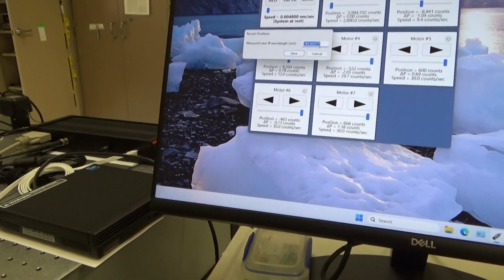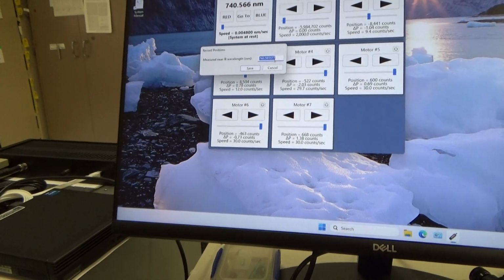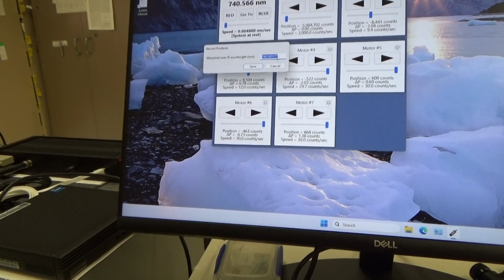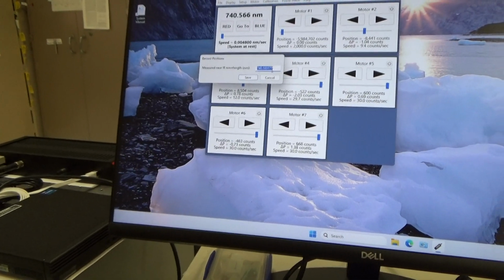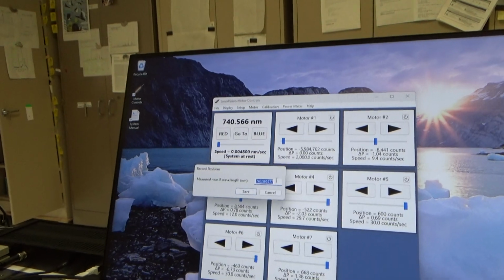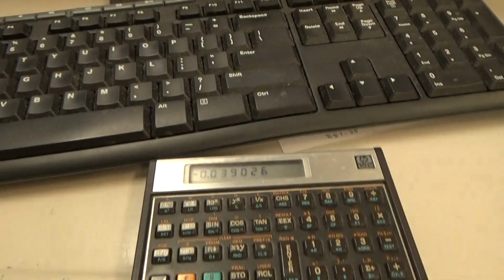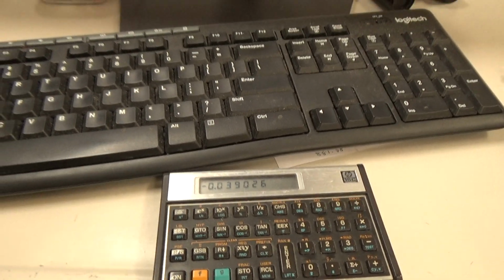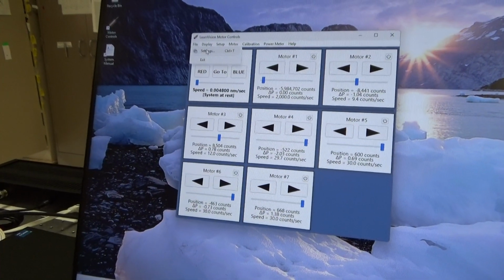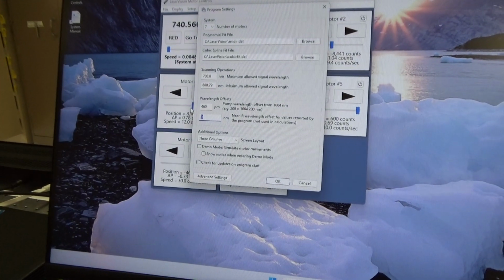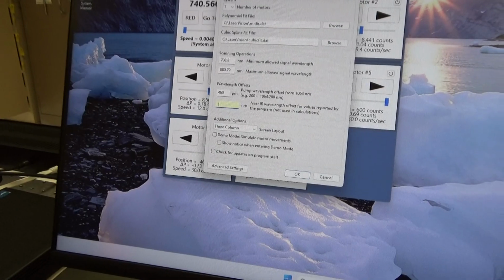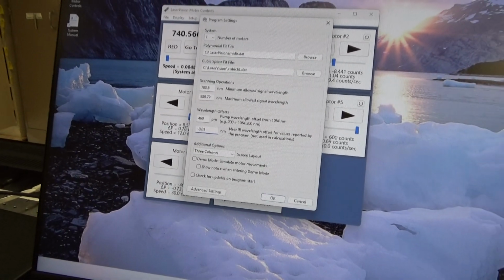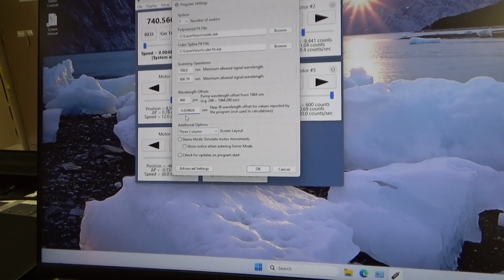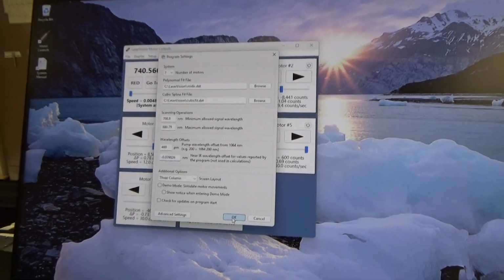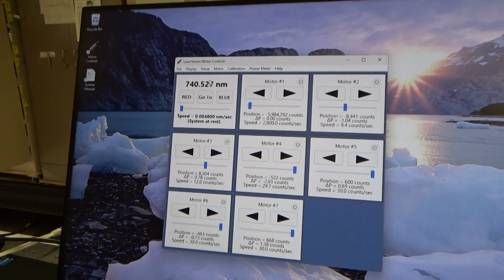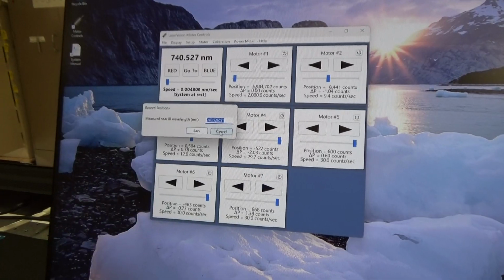So let me just type in 740.565577. And so I want to go to a smaller value, and so I need to subtract off 0.039 nanometers from the curve. I can displace the curve simply by going into the settings file here and adding in a near IR wavelength offset. So I'll put this in minus 0.039026. And if I've done the sign correctly here, it should read 740.5265277. Okay, fine. 526551. That's what I wanted.